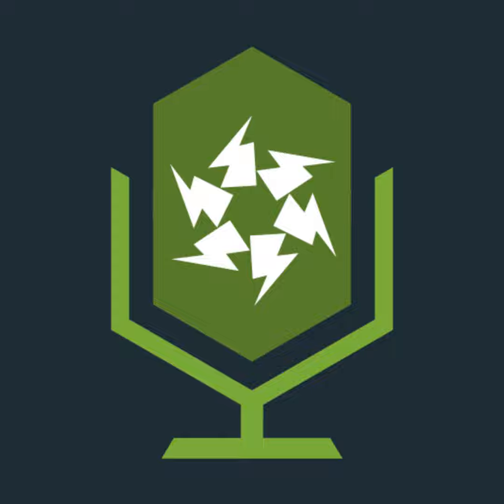Okay, so the way to approach it is always the same, and let's remember the basics. We must remember coordination: IB is less than or equal to IN, which is less than or equal to IZ. Let's remember that as a starting point. We also know that we need a circuit, so let's go with a piece of equipment such as a heater. Let's call this heater 10 kilowatts at 230 volts.